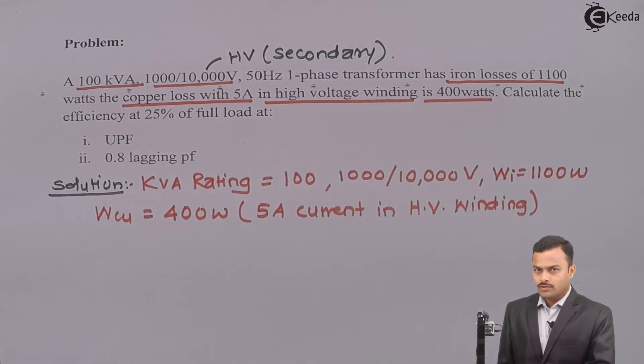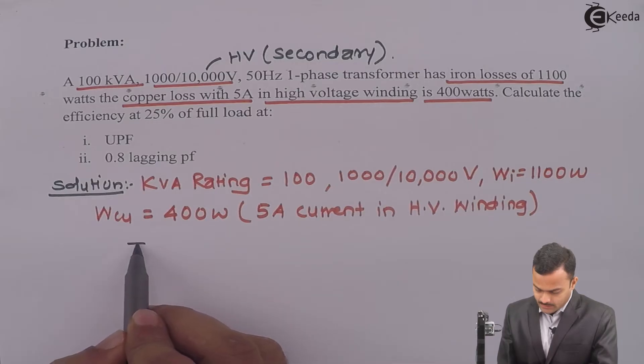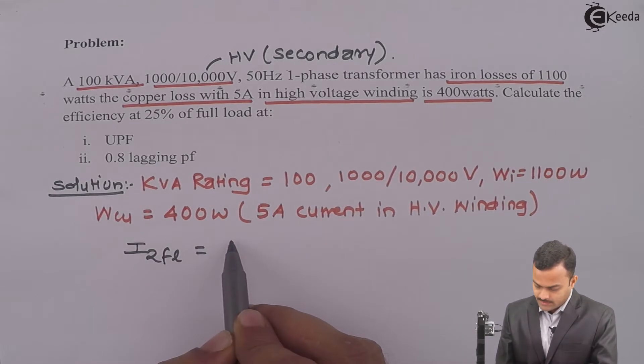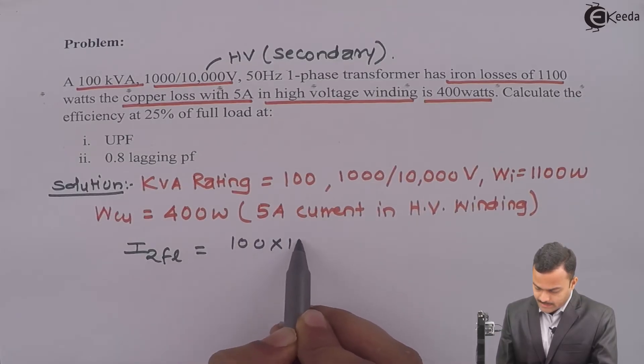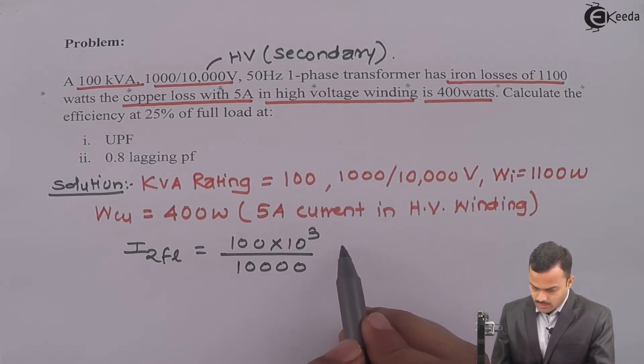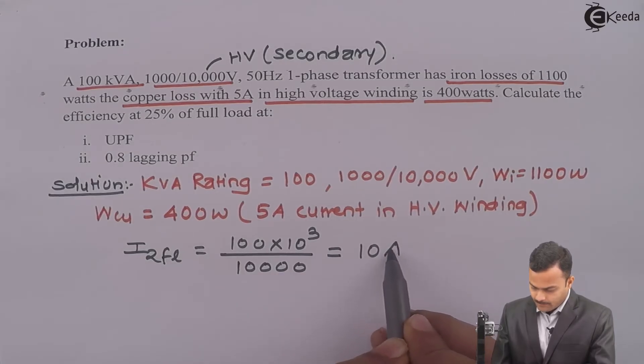So I need to find out the full load copper loss with respect to secondary full load current. This thing you have to keep in mind. So first we will do that. First I will calculate secondary full load current, which is KVA rating divided by secondary voltage, which is 10000. So if you solve, you will get I2FL as 10 ampere.